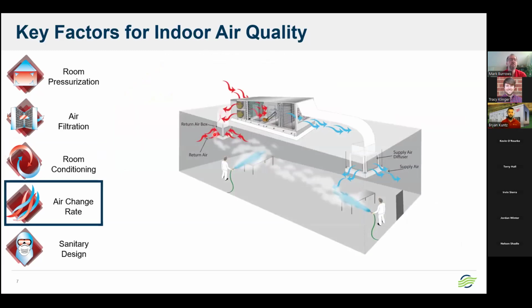Air change rate. This is really critical, especially when bouncing between sanitation and process shifts. For those that don't know, during a normal process period, we're talking about 45-degree rooms, right? At night, or whenever sanitation comes into play, those process rooms shut down for the day. Sanitation shifts will come in with 140-degree water temperatures to spray down the in-room equipment, floors, walls, ceilings, pretty much everything in those rooms. And when you do that, you're certainly going to create a fog bank, a lot of moisture that you need to evacuate from the room.